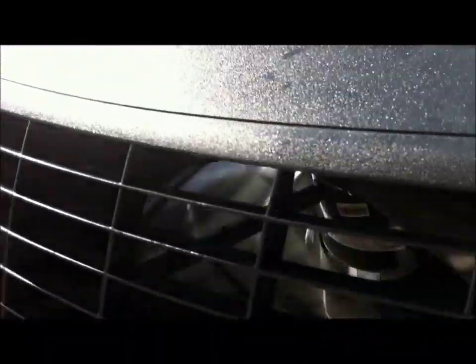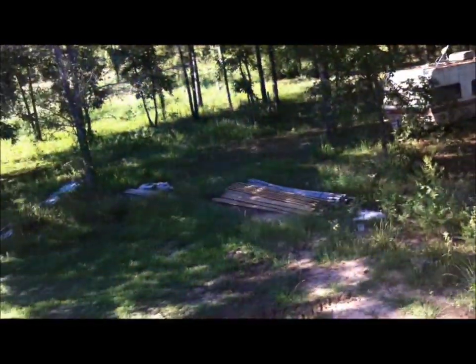Alright, there's the inside. We're going to climb up one more time, finish cleaning up, take another look. Target subcool on these units is 9 — we're at 9. Eight degree superheat. So I'm happy. Sweet job.